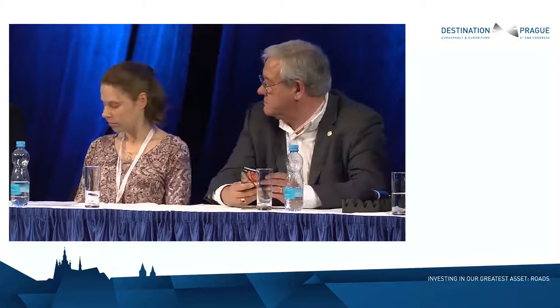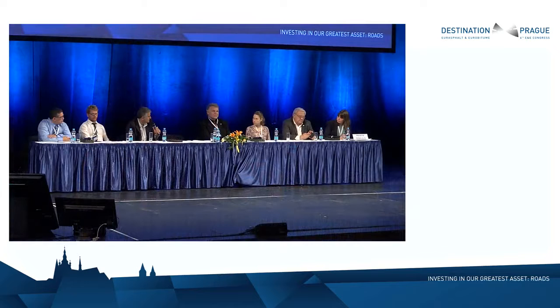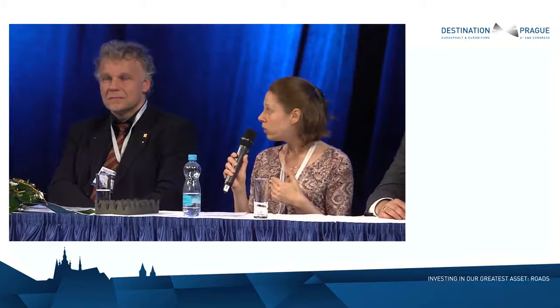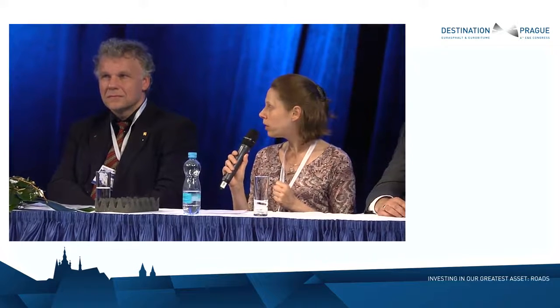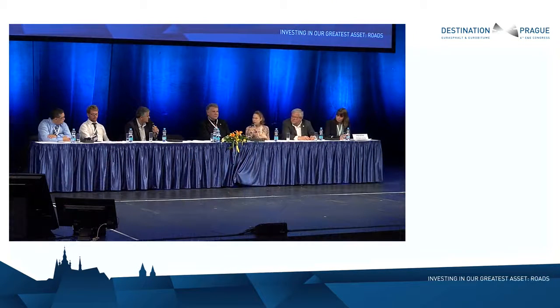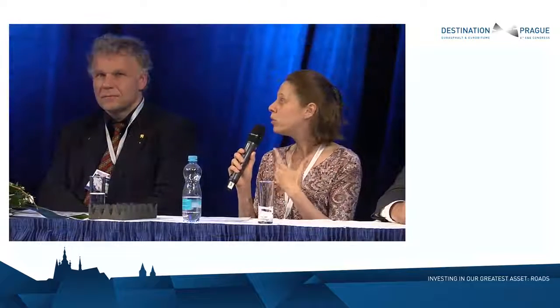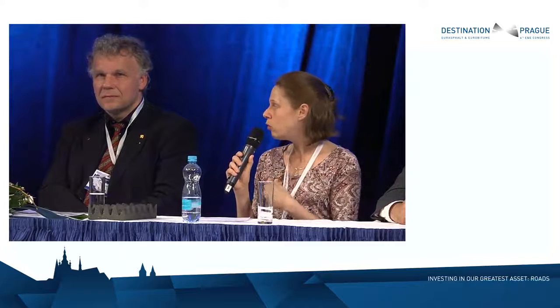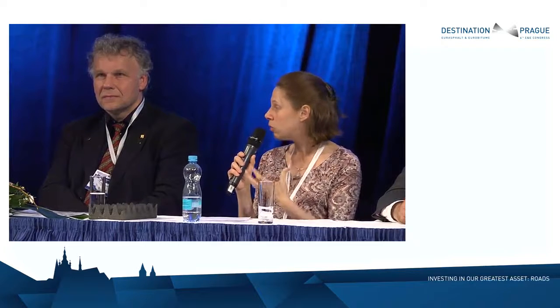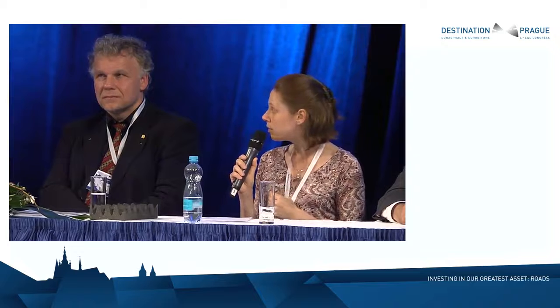Maybe I missed it, but how do you control the temperature 40 millimeters deep in a field test at 20 degrees C? For the LAMI? For which test? For the field test, yeah. For the field test, the LAMI is only an on-site test. For the SBT and the TAT, the tests are performed in the laboratory in a controlled chamber. So for the LAMI test, there is no set temperature? For a LAMI test, you can perform it in the laboratory at 20 degrees, but on the field you are using the field temperature. But there is what we call a correction factor, and you can correct your resistance to 20 degrees. It's written in the pre-standard.